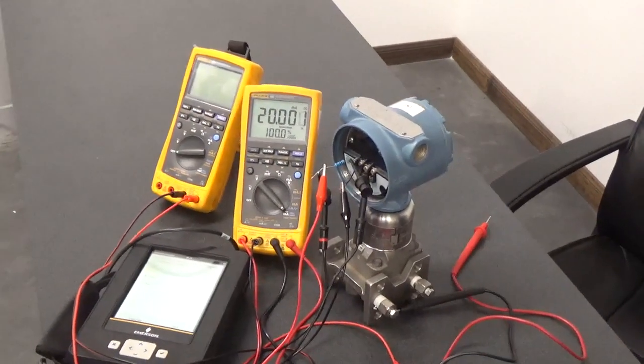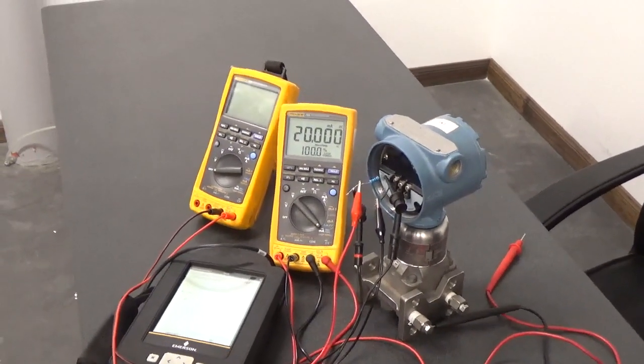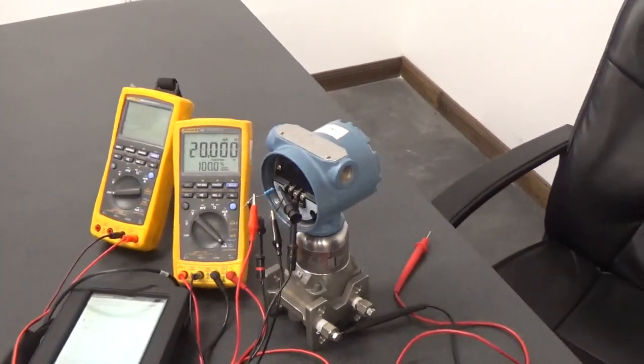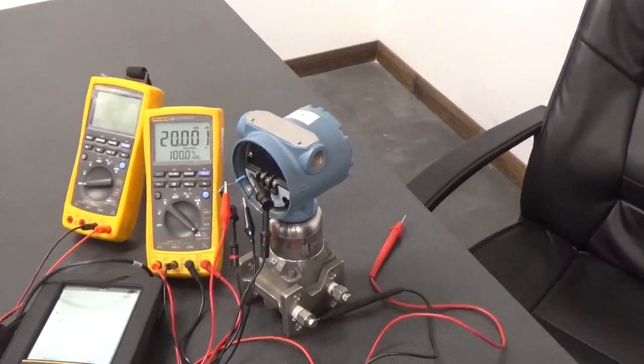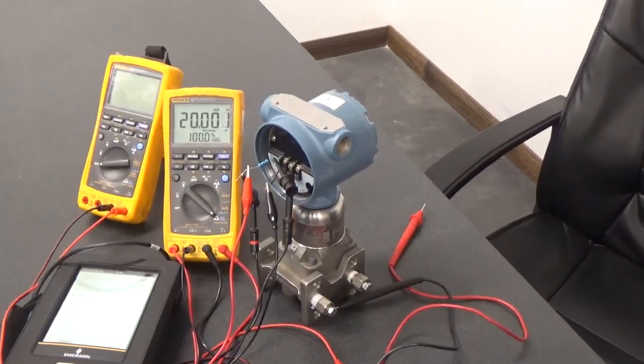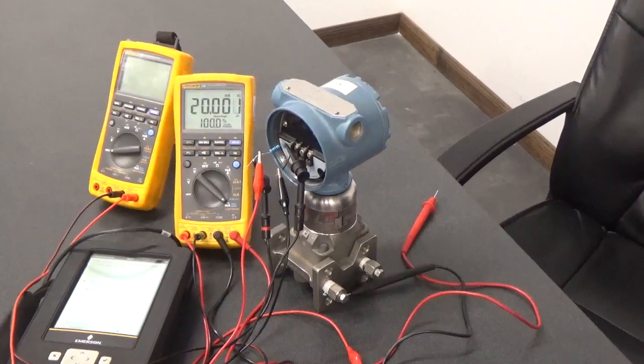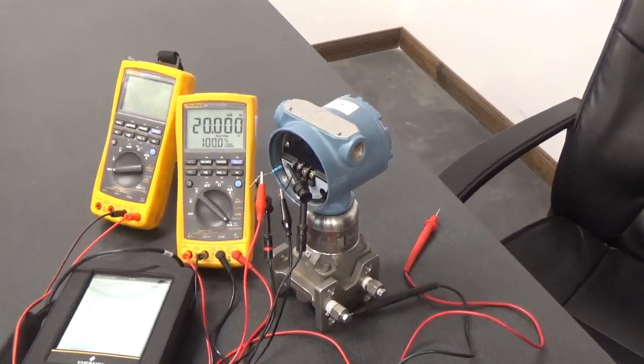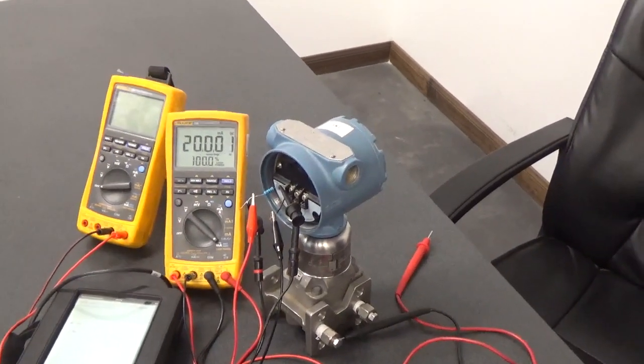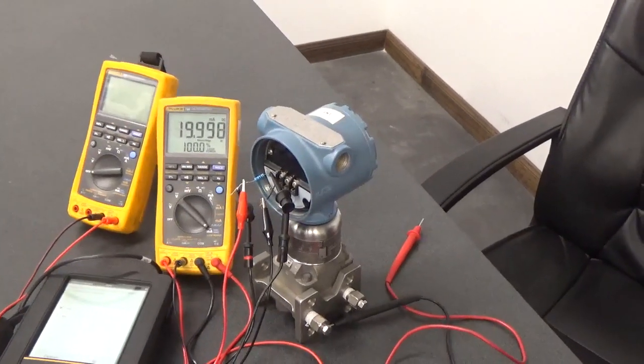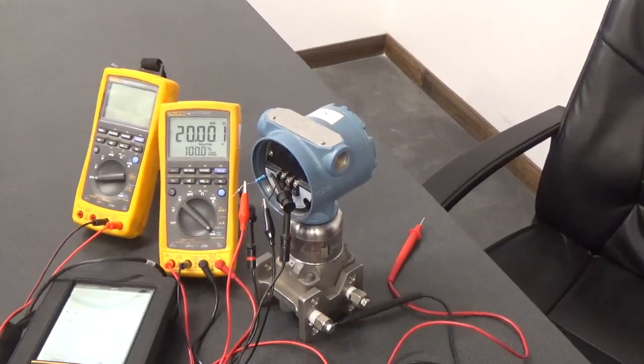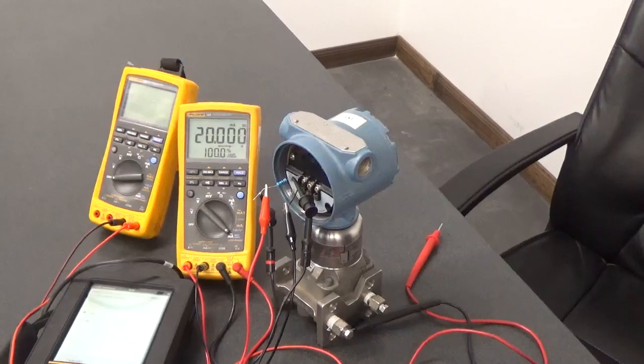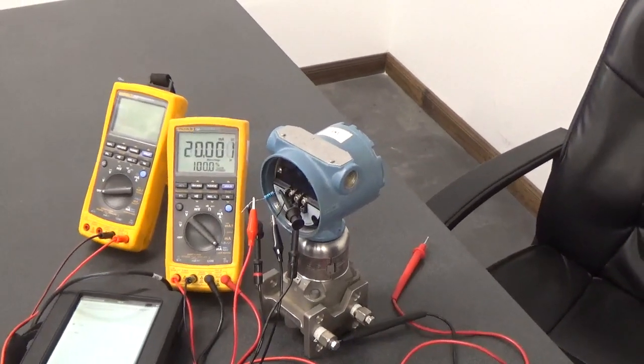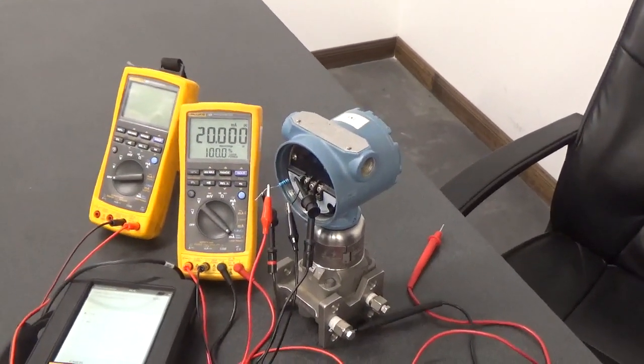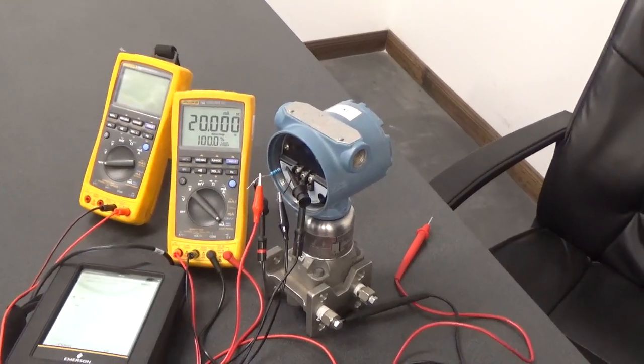That's good? A calibration is not complete unless you check this at least. I'm not saying that you have to calibrate it every time, but you need to check it. You gotta give it a bad signal? No, you don't check it by giving it a bad signal. I gave it a bad signal because I wanted you to see a bad milliamp signal. Okay. You don't give it a bad signal. If you go to the field and you check it and the signal's bad, well then you need to calibrate it. Yeah. And you know how to do it.